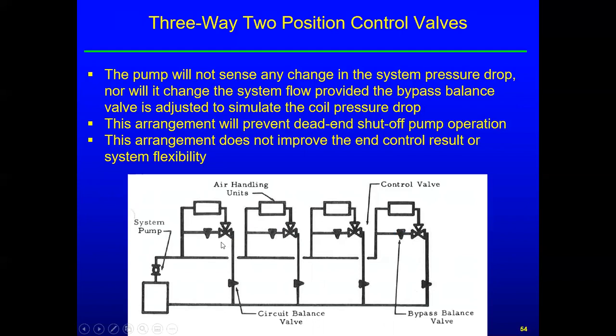So you can't deadhead the pump, and you don't get any better control or system flexibility, but you do protect the pump, even though you're probably wasting energy, because you're pumping the same flow all of the time, which is more than you need, except at design conditions.